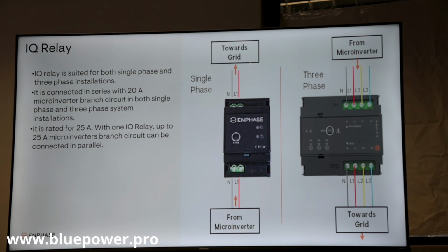For three phase, you can times that by 3 per branch. So 10 times 3 would be 30 microinverters in one branch for three phase. And for the bigger product, you can do 3 times 8, 24. So you can start thinking in terms of 10s or 30s or 8s or 24. And that's how you piece together your branches.